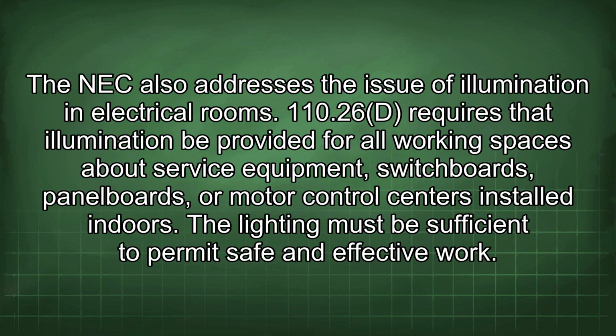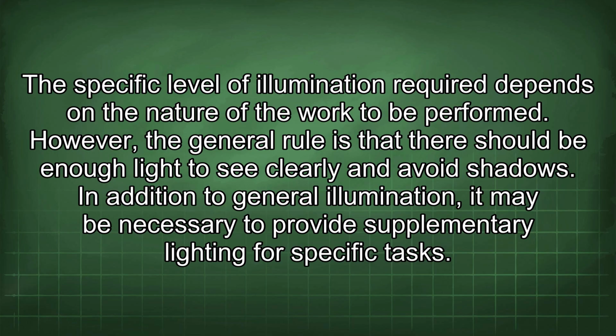The NEC also addresses the issue of illumination in electrical rooms. 110.26(D) requires that illumination be provided for all working spaces about service equipment, switchboards, panelboards, or motor control centers installed indoors. The lighting must be sufficient to permit safe and effective work. The specific level of illumination required depends on the nature of the work to be performed. However, the general rule is that there should be enough light to see clearly and avoid shadows.